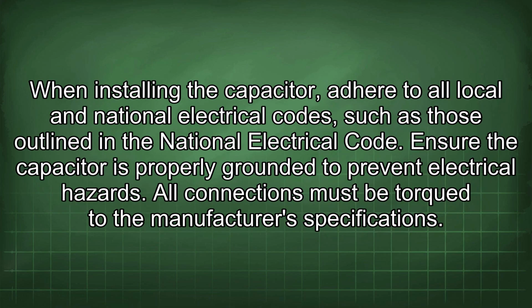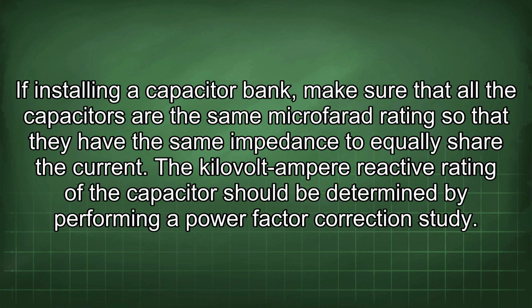When installing the capacitor, adhere to all local and national electrical codes, such as those outlined in the National Electrical Code. Ensure the capacitor is properly grounded to prevent electrical hazards. All connections must be torqued to the manufacturer's specifications. If installing a capacitor bank, make sure that all the capacitors are the same microfarad rating so that they have the same impedance to equally share the current.